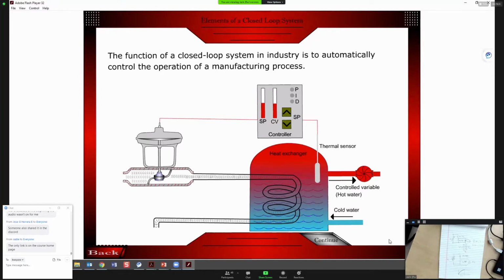You have the 4 basic elements down there. Through this example, we're going to take a look. So this is a basic heating system. We have cold water coming in, then hot water coming out. We're using a controller to control a valve to let in steam or a heating element. Here is the heat exchanger tank. There's a pipe down here that exchanges the heat between this one and the domestic water. We have a temperature sensor down here. Based on this temperature sensor, the controller makes the decision how far this valve will open to let steam in.